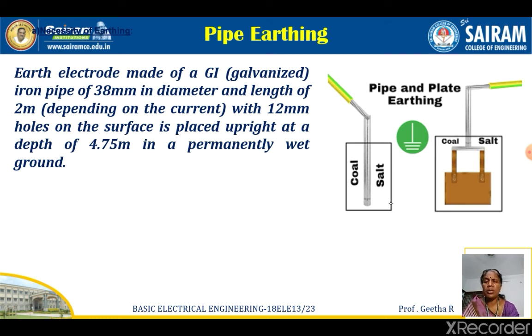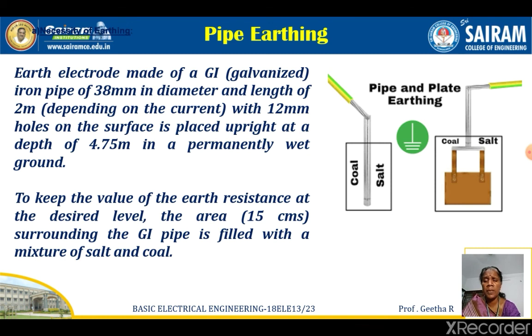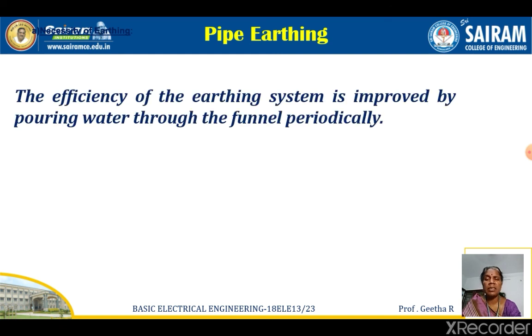Here the earth electrode is made of a galvanized iron pipe of 38 millimeter diameter and a length of 2 meter, with 12 millimeter holes on the surface. It is placed upright, that is, vertically, at a depth of 4.75 meter in permanently wet ground. To keep the value of earth resistance at the desired level, the area of 15 centimeters surrounding the GI pipe is filled with a mixture of salt and coal. The efficiency of the earthing system is improved by pouring water through the funnel periodically, like plate earthing.